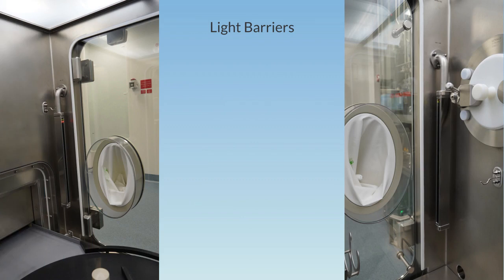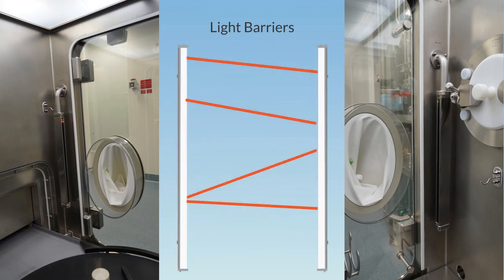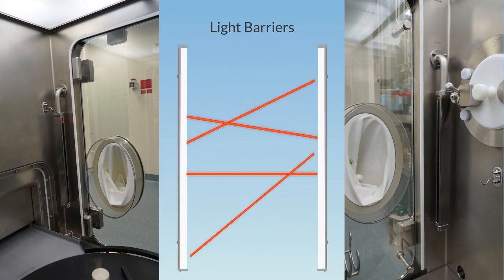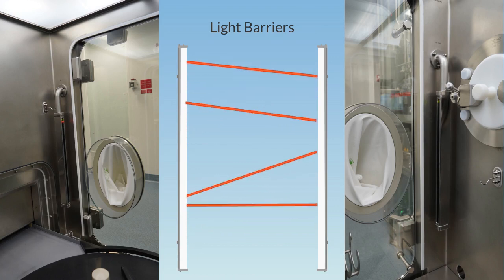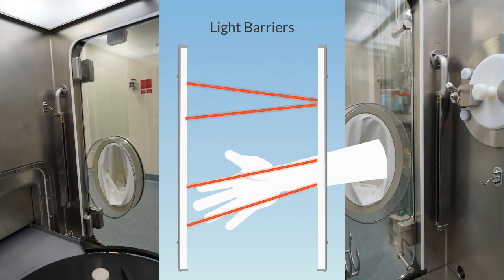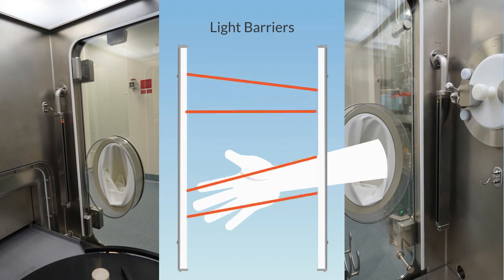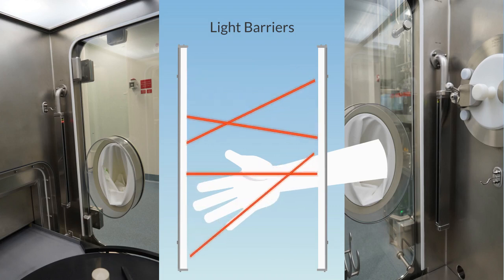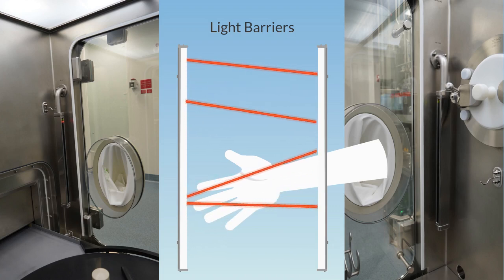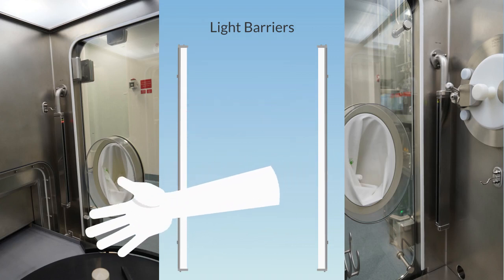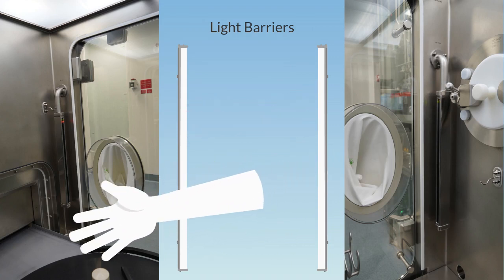To protect the operator from machinery hazards, the glove ports of the isolator are monitored by two separate safety loops. On the inside of the isolator, there are light barriers, and at the outside of the isolator is a control system to check the positions of the glove extenders. During production mode, the inner loop is active so that the machine stops when the light barrier is interrupted.